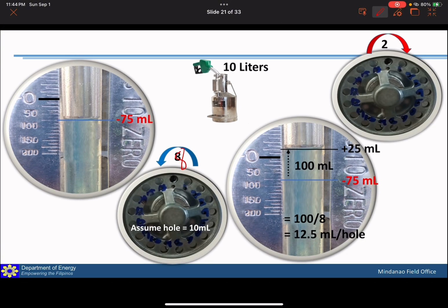Again, initial reading is minus 75 ml. After adjusting it 8 times, because we assume 10 ml yung value per hole, the new reading is plus 25 ml. Therefore, may 100 ml adjustments. So 100 ml divided by 8 holes, the actual value per hole is 12.5 ml. Then we need to rotate it clockwise twice, because 25 divided by 12.5 is 2, para mabalik siya sa 0.